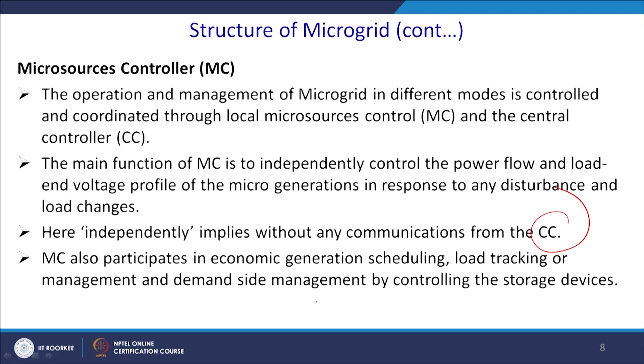MC also participates in economic generation scheduling, load tracking or management, and demand side management by controlling the storage devices. It may also ensure that each microsource rapidly picks up its generation to supply its share of load in standalone mode and automatically comes back to the grid connected mode with the help of central control. The most significant aspect of MC is its quickness in responding to the locally monitored voltages and currents, irrespective of the data from the neighboring MCs. So, this is the most important feature.